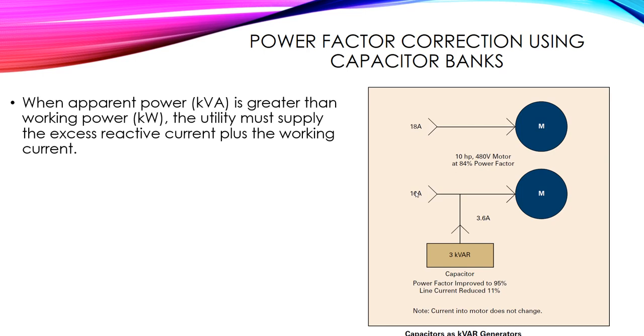The benefit here is that we reduced the amount of apparent power absorbed from the grid, and we also reduced the amount of current, giving us a lower voltage drop and a better power factor. By adding a 3 kilovar capacitor, the power factor improved to 95 percent and the line current reduced by 11 percent.